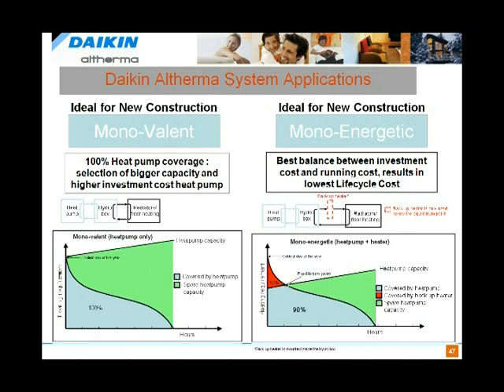On your y-axis, the heating requirements, and then the number of hours being employed during the year, x-axis. And in this case, we're using entire heat pump capacity. We will have no backup on this system. So maybe that relates to if somebody doesn't want to have any backup, they can be sized such.